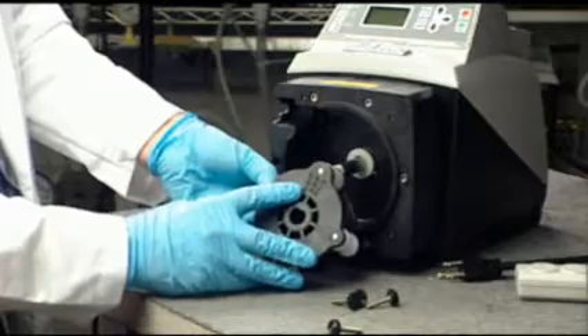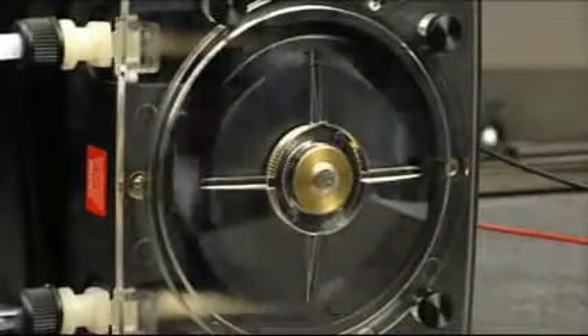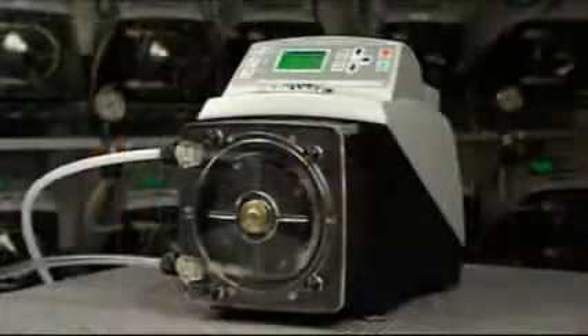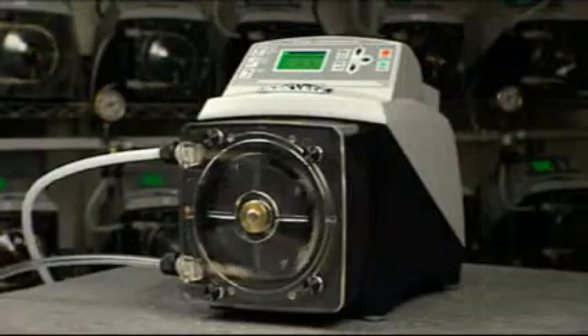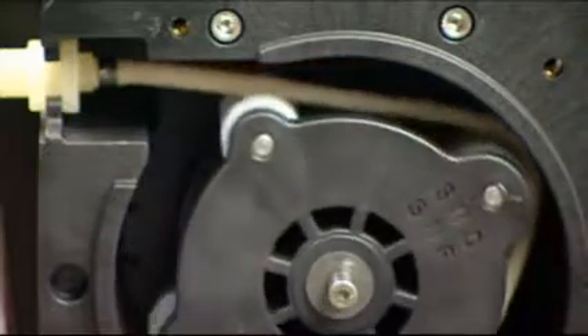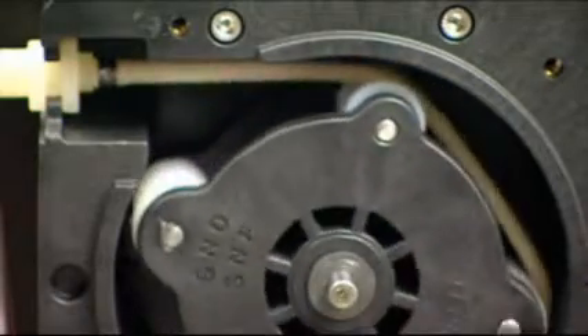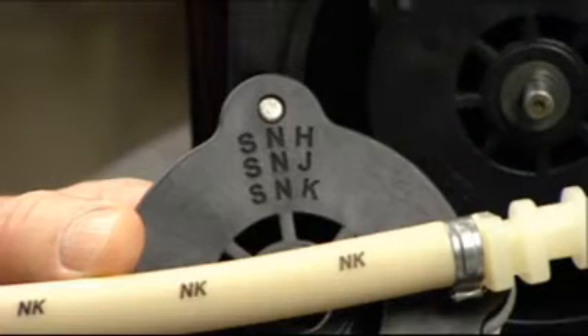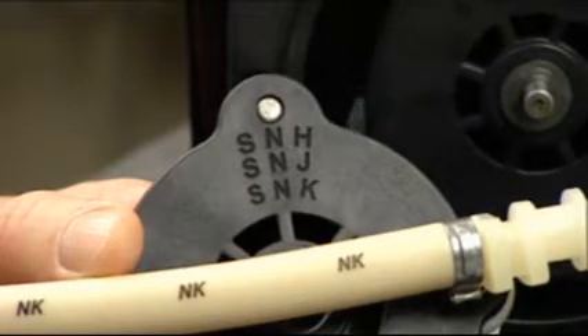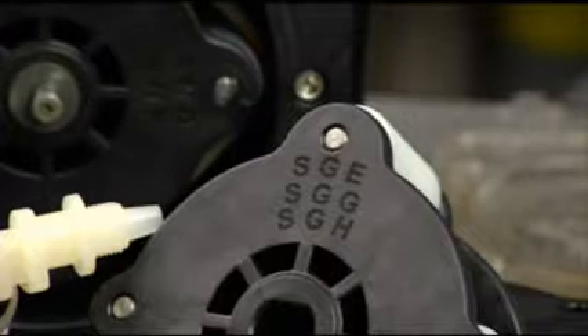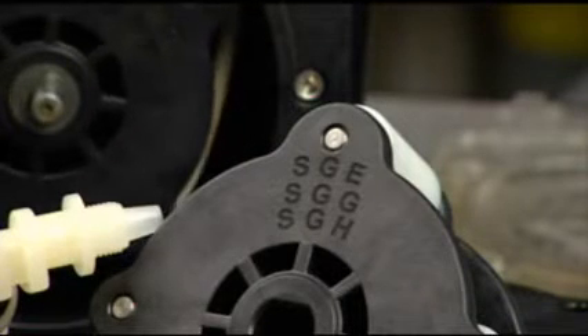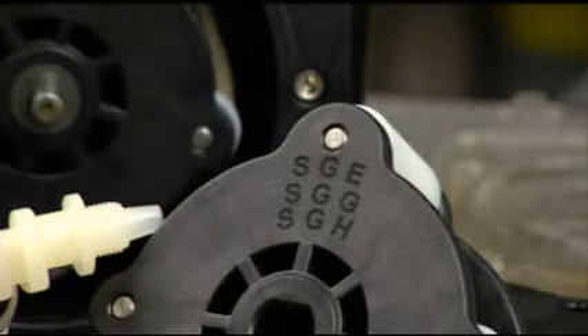Each roller assembly is stamped with 3 letters. These letters indicate the pump and tube that can be used with the roller assembly. The first letter S indicates the A3 series pump head. ND and NF tubes use 1 roller assembly. NH, NJ, and NK tubes use a second roller assembly. And GE, GG, and GH tubes use a 3rd roller assembly.